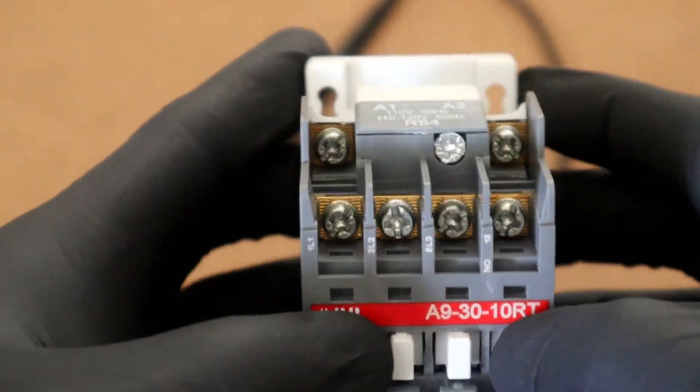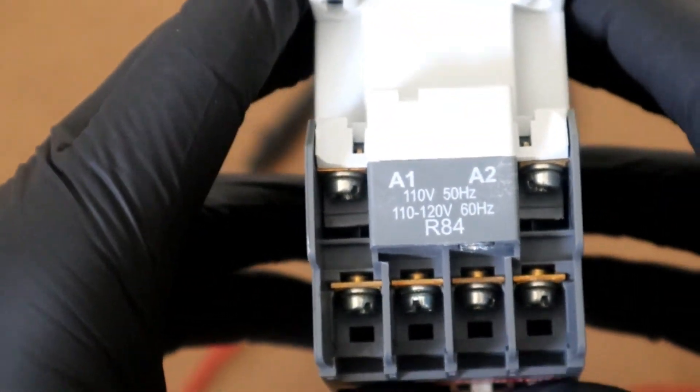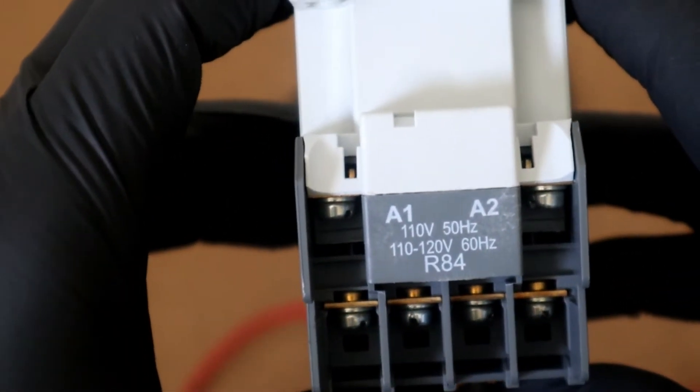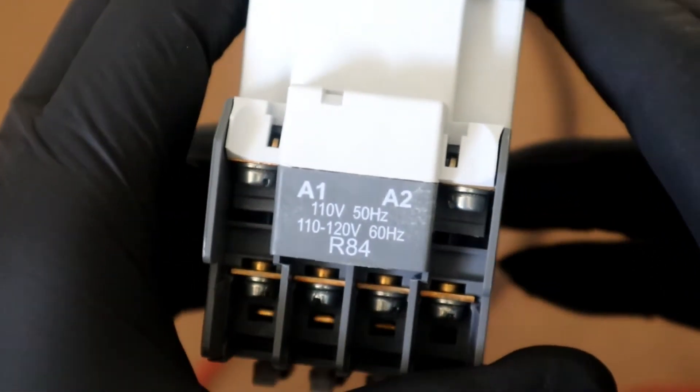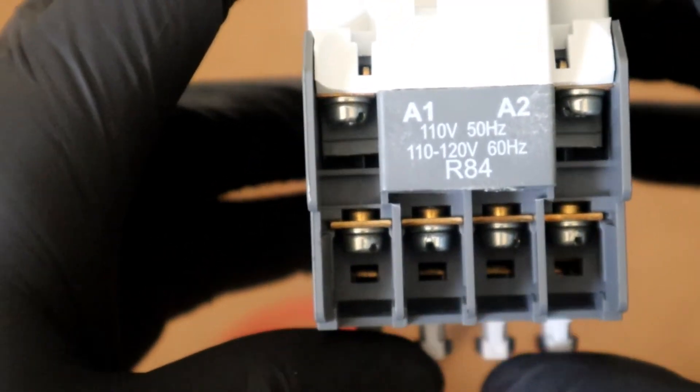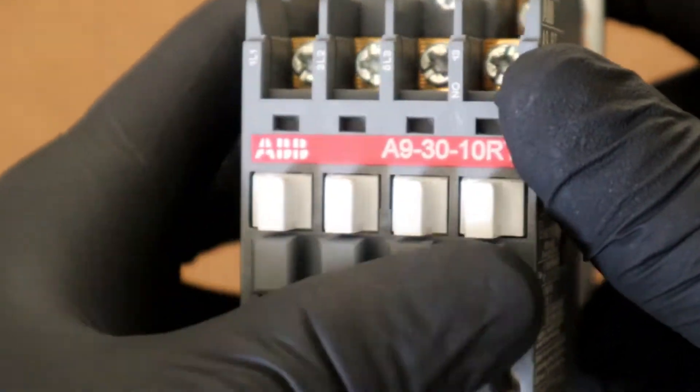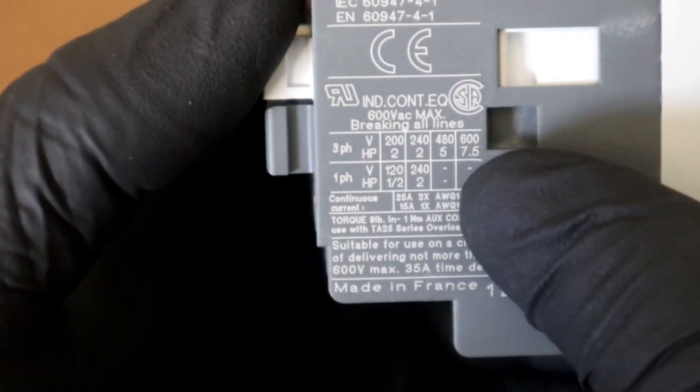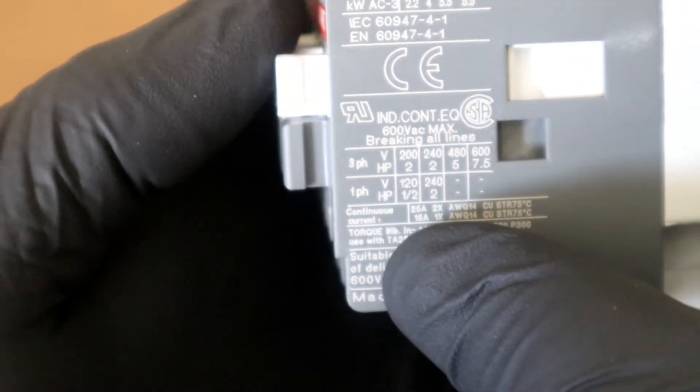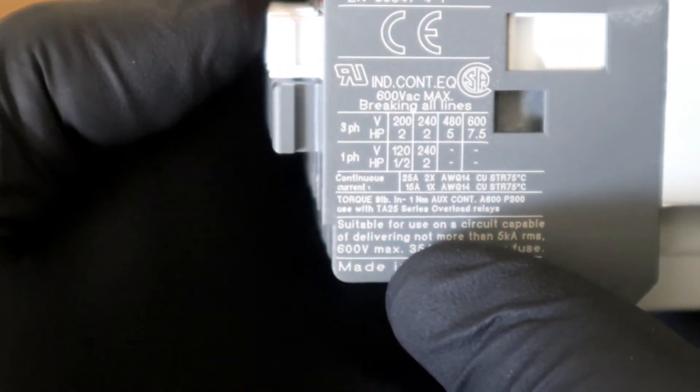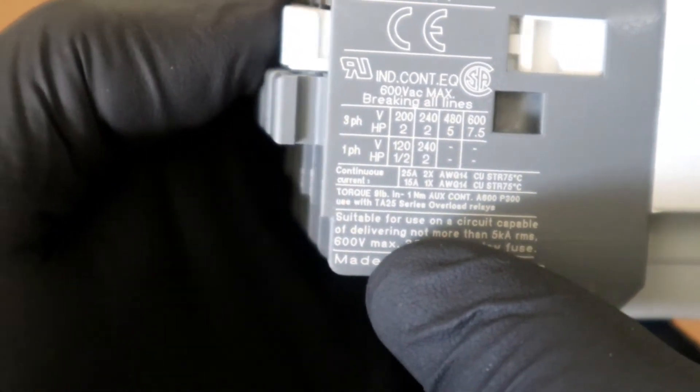Another point to note, when using a contactor, it's always good to check your manufacturer specifications or if it's a replacement part, check the specification in the contactor that is being replaced. So that the coil voltage levels match up as well as the high current parts, ensure that the voltage specifications are intact. You can see this contactor can switch three phase or single phase with different voltage levels for the three phase ranging from 200 to 600 volts, and for the single phase 120 volts.